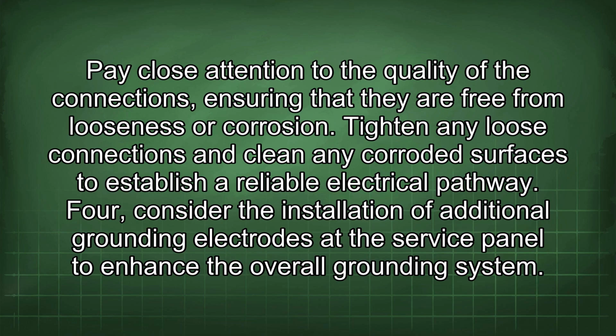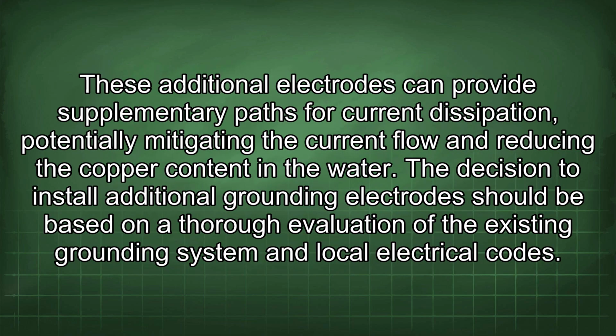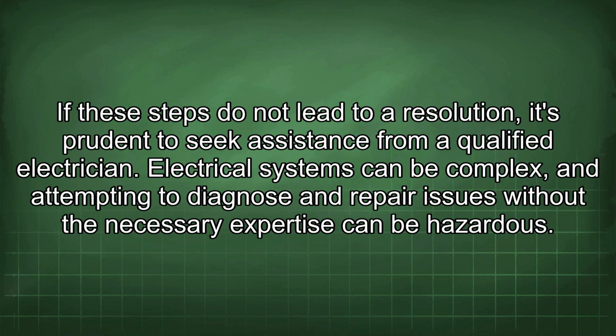4. Consider the installation of additional grounding electrodes at the service panel to enhance the overall grounding system. These additional electrodes can provide supplementary paths for current dissipation, potentially mitigating the current flow and reducing the copper content in the water. The decision to install additional grounding electrodes should be based on a thorough evaluation of the existing grounding system and local electrical codes. If these steps do not lead to a resolution, it's prudent to seek assistance from a qualified electrician.